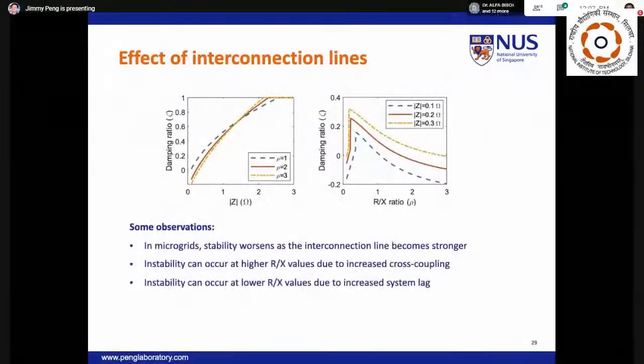We will now look at the impact of the lines interconnecting the grid-forming inverters in the microgrid. This is when things become really interesting. In general, the stability of the system worsens when the line becomes more dominant. This can occur at a higher Rx ratio, which increases cross coupling effects, or at a lower Rx ratio where the system lag is increased.